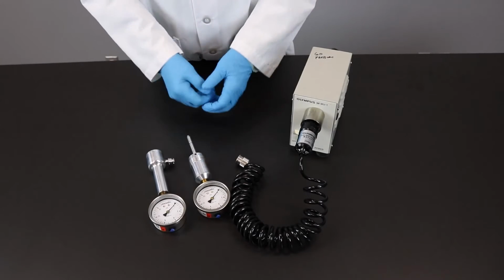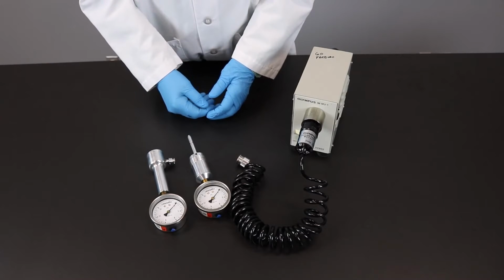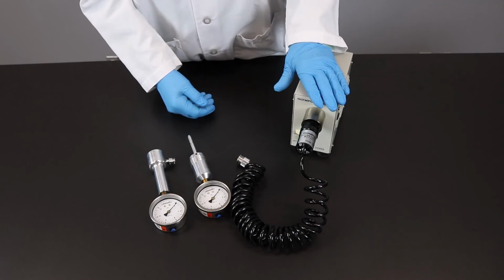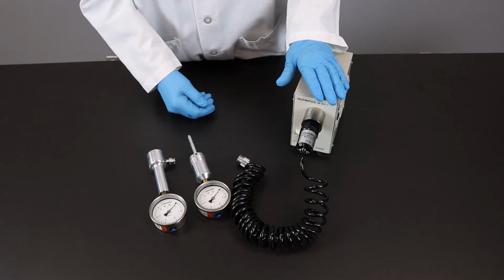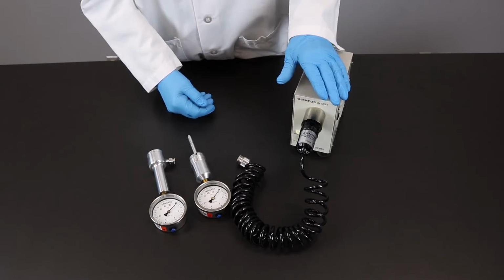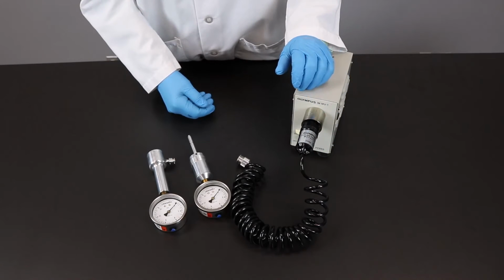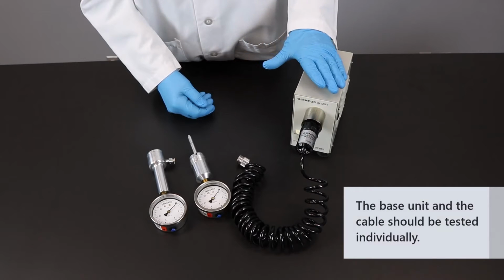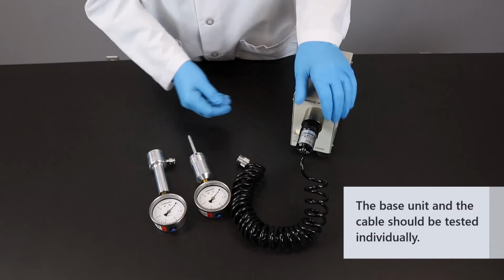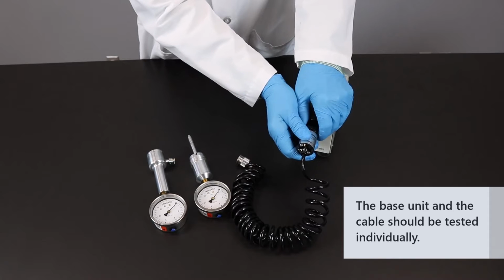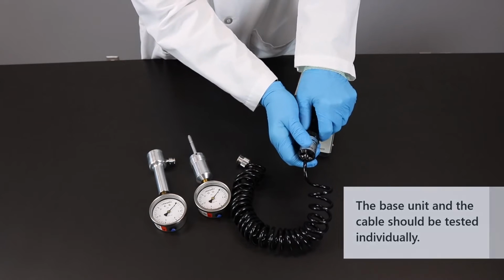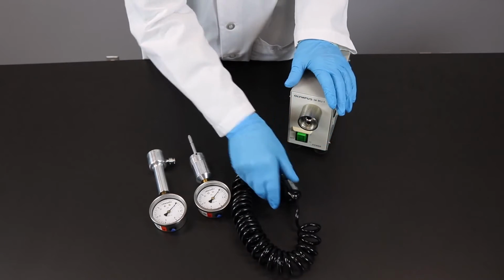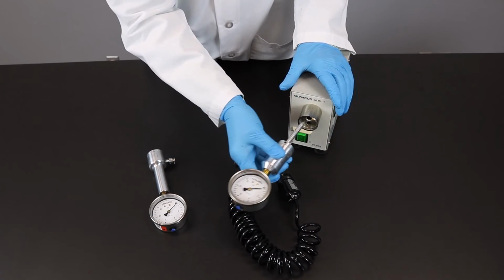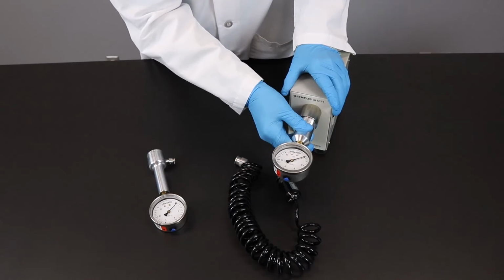So we're going to start by showing use of the leak tester to test one of the most commonly used automated leak testers that's out there, the Olympus MU1 base unit and the MB155 cable. In order to do this, we need to test each of these individually. So we're going to start by testing the base unit, the pump, by removing the cable and inserting the leak tester with the stem into the base unit.